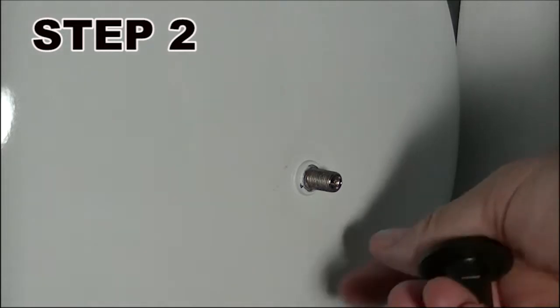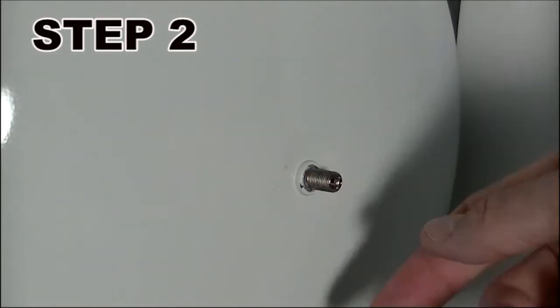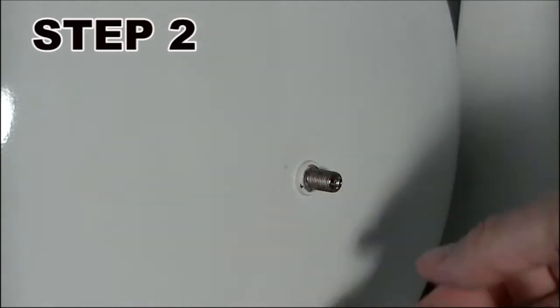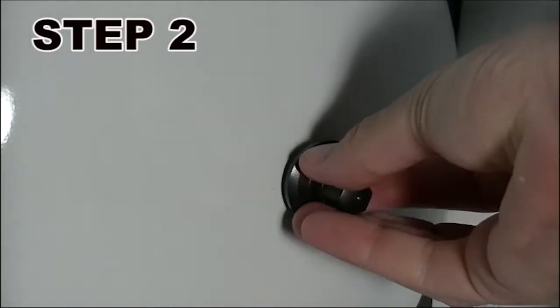While system is pressurized, test the Schrader valve on all accumulator tanks to ensure no water leaks out. Depress the pin in the center of the valve. If water leaks from the Schrader, then you will need to replace the accumulator tank.